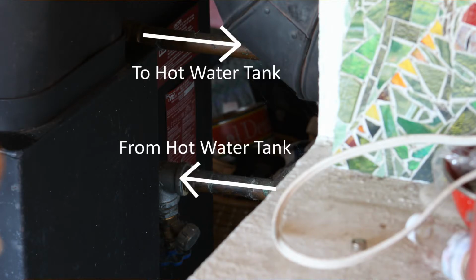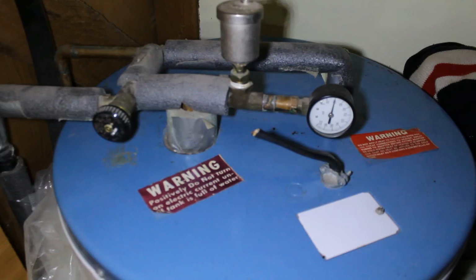We've designed the system so the top of both the pipe in the firebox of our wood stove and the heat exchanger have pipes leading to the top of the hot water tank. There are exit pipes from the bottom of the hot water tank down to the bottoms of each of those. The only reason it flows in that direction is because of the thermosiphon and how heat is added to the system. The top of the hot water tank has the hottest water, so that's where we pull the exit from to our taps.